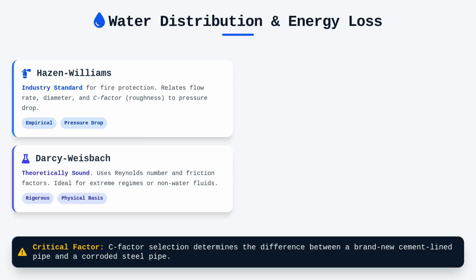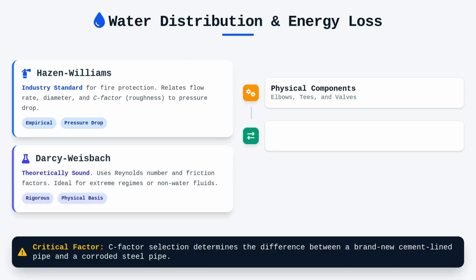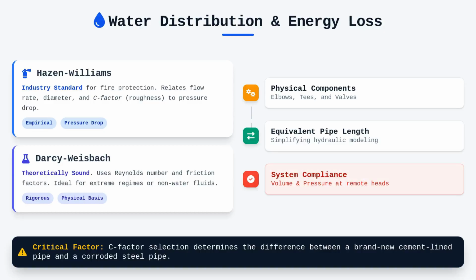In complex piping geometries where you have elbows, T's, and various valves, we convert these physical components into equivalent pipe lengths to simplify the hydraulic modeling process. Managing these calculations correctly is the difference between a compliant system and one that lacks the necessary volume and pressure at the most remote sprinkler head.